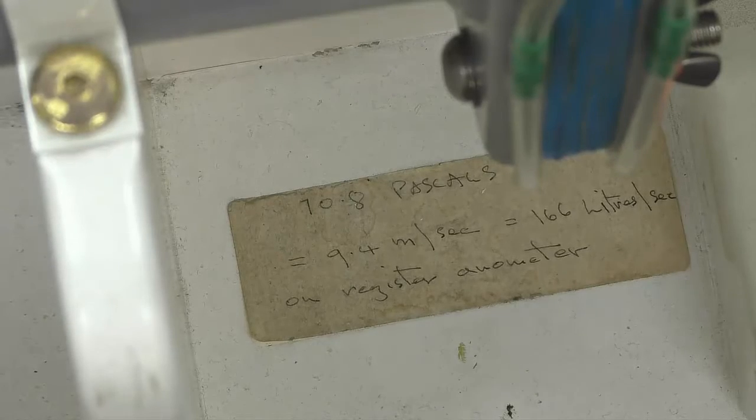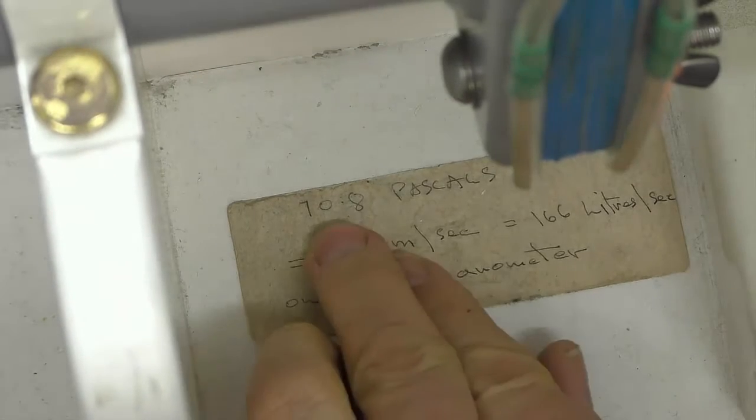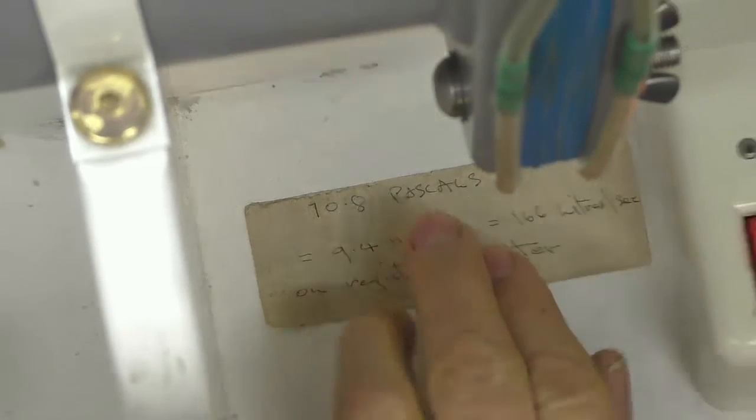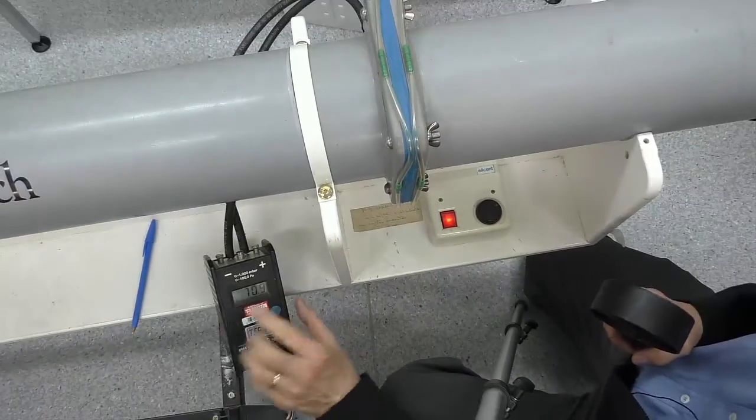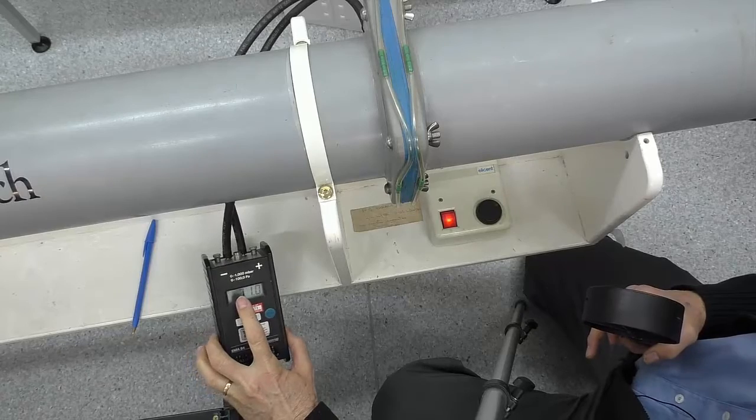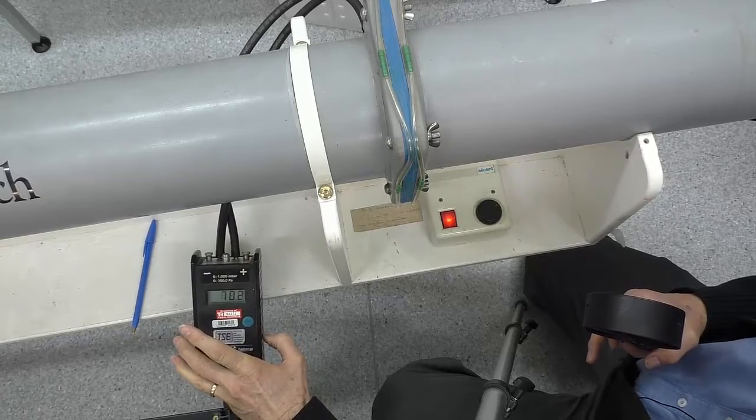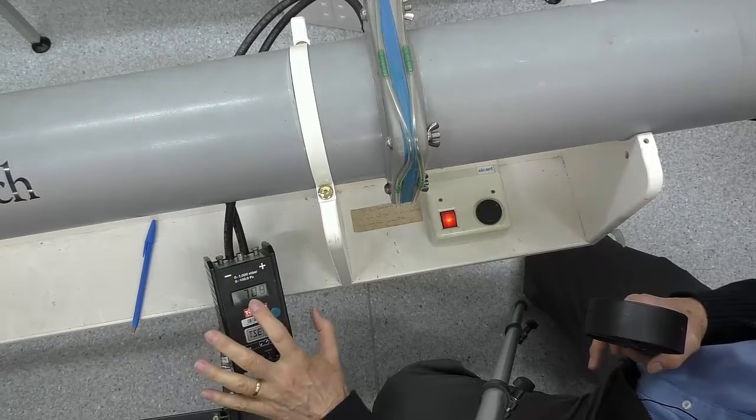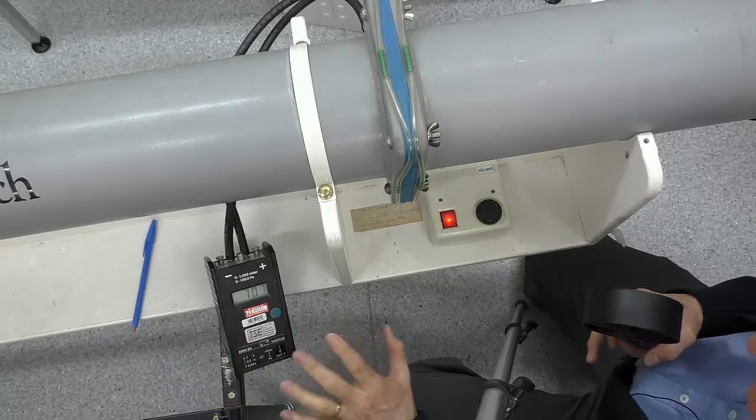Okay, this is our reference airflow rig. When we have 70.8 pascal across the orifice plate here, as measured using this manometer, that moves around a fair bit, but it's around 70.8. You can see that there's a fair bit of movement in that, but that's pretty close.